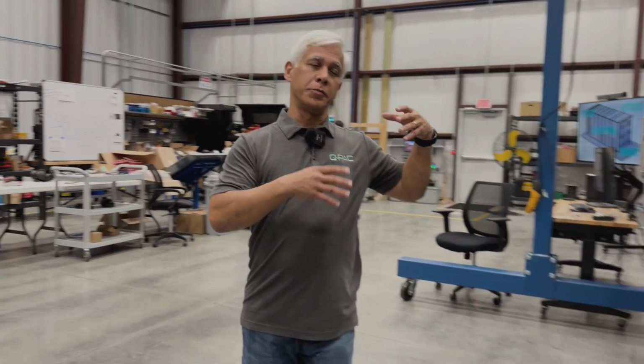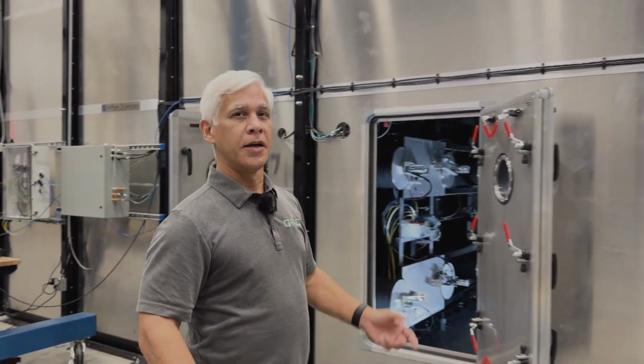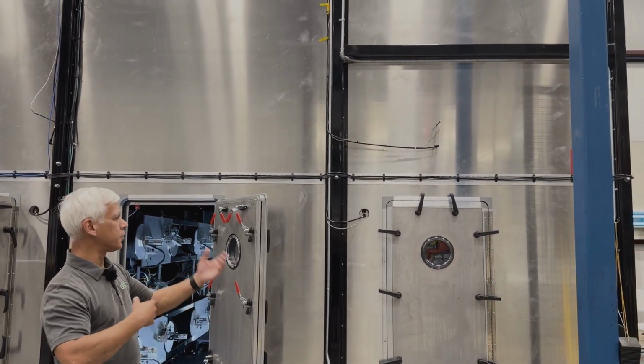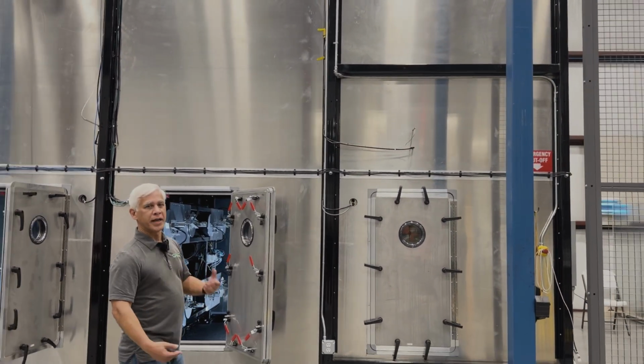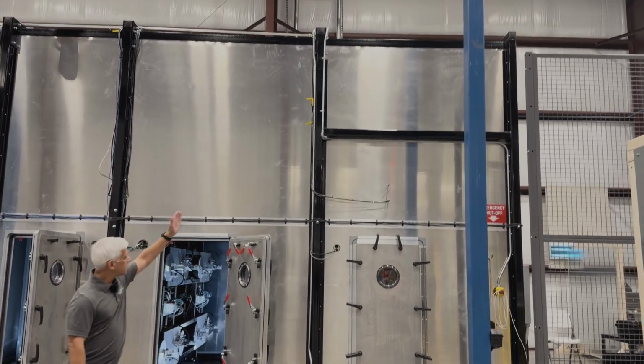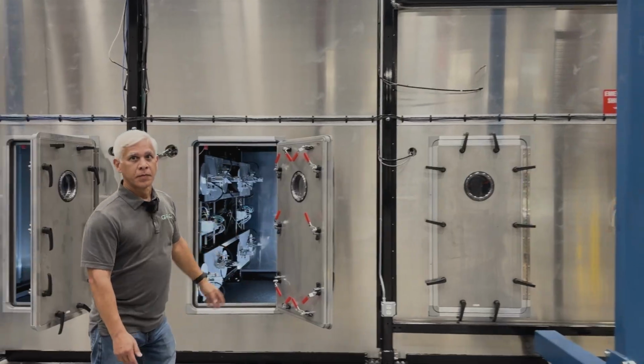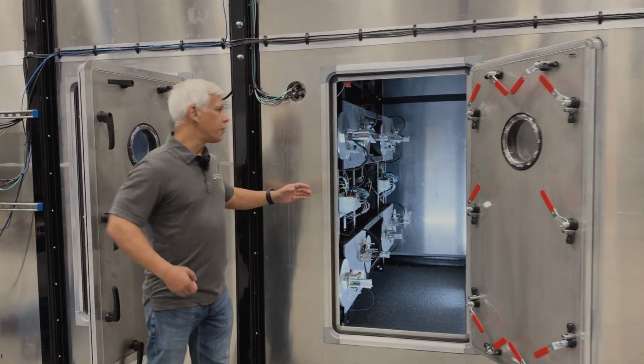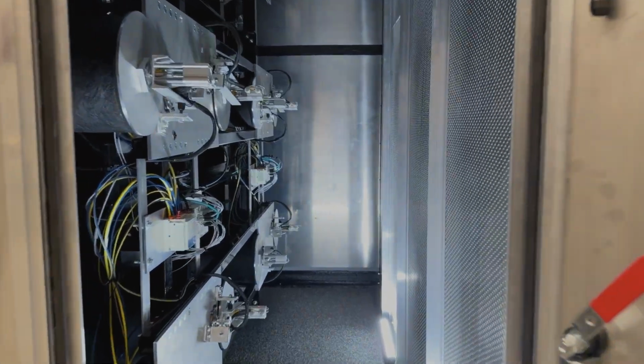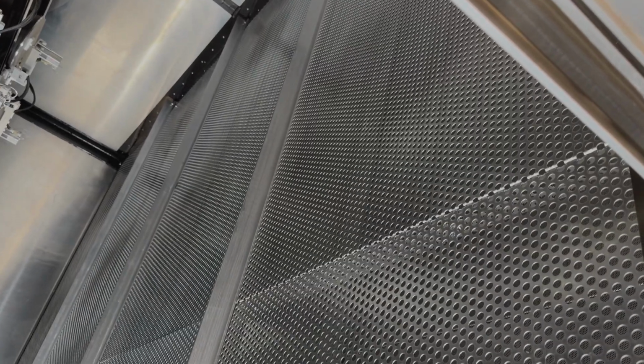It's important, it's imperative really, when we're testing the fan that we know what the airflow is going into the fan. If the air is turbulent, if it's flowing around backwards and forwards, your results are not repeatable. You can't really trust the results. So in this section behind this beam here, we have a series of flow straighteners. And so you'll be able to see some of that coming through here. Looking to the right here, you'll see an aluminum grid there. Behind that, there's a finer grid. And behind that, there's yet a third grid. And all that's doing is dispersing the air so that it hits the fan, passes through to that 12 by 12 foot section. On the other side, it's coming out even. So that every fan that we have in the array is seeing the same airflow.